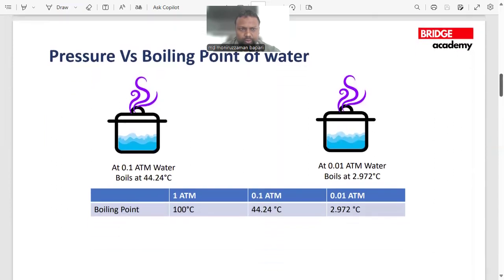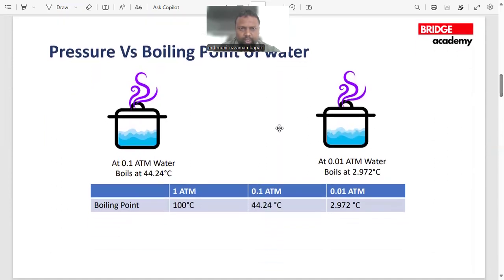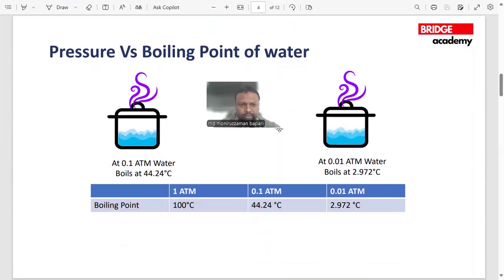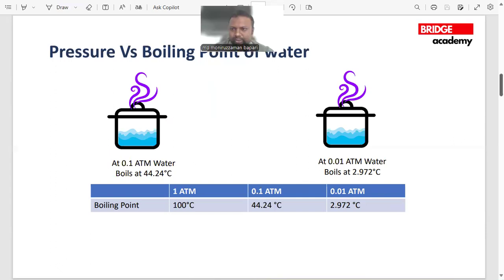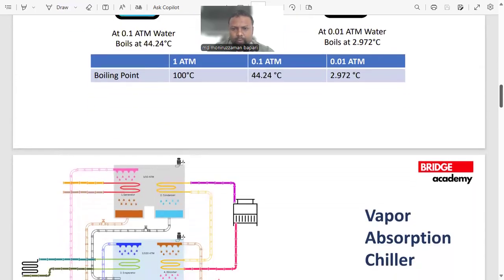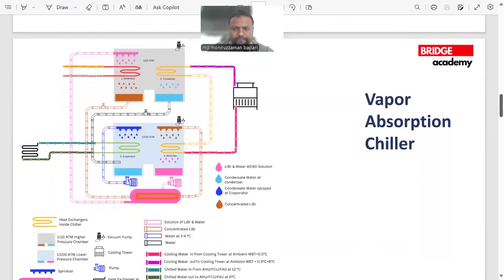Now also, let's look back at pressure versus boiling point of water, the relation between them. So boiling point of water at 1 atmospheric pressure is 100 degrees centigrade. Remember, if the pressure goes low, the boiling point goes low. So at 0.1 atmospheric pressure, the boiling point is only 44.24 degrees centigrade. However, at 0.01 atmospheric pressure, the boiling point is as low as 2.9 degrees centigrade. So these are the basic stuff that we need to learn to understand the working principle of vapor absorption chiller.